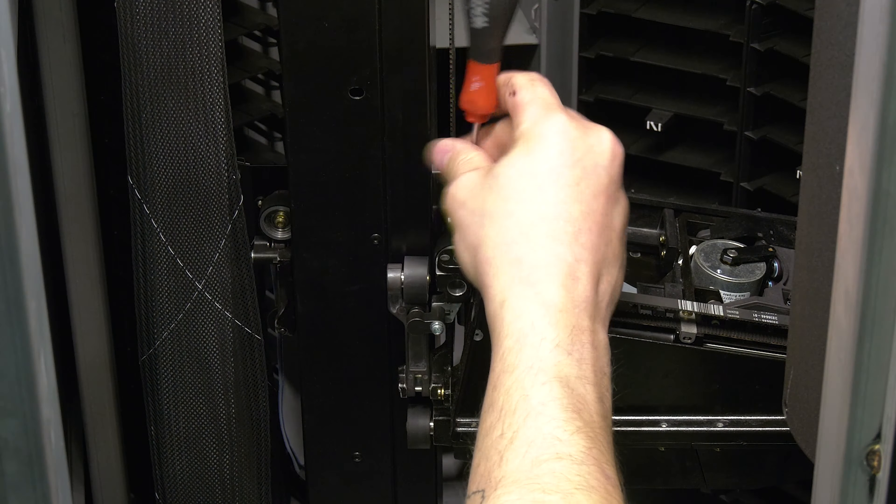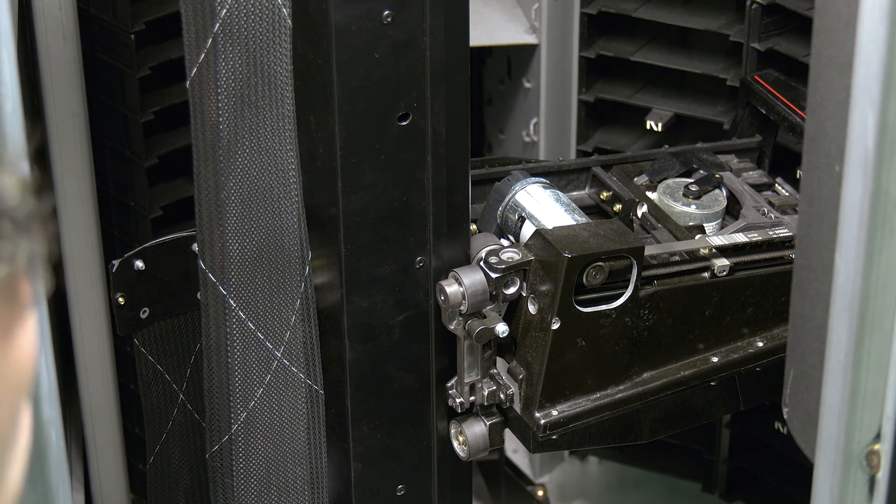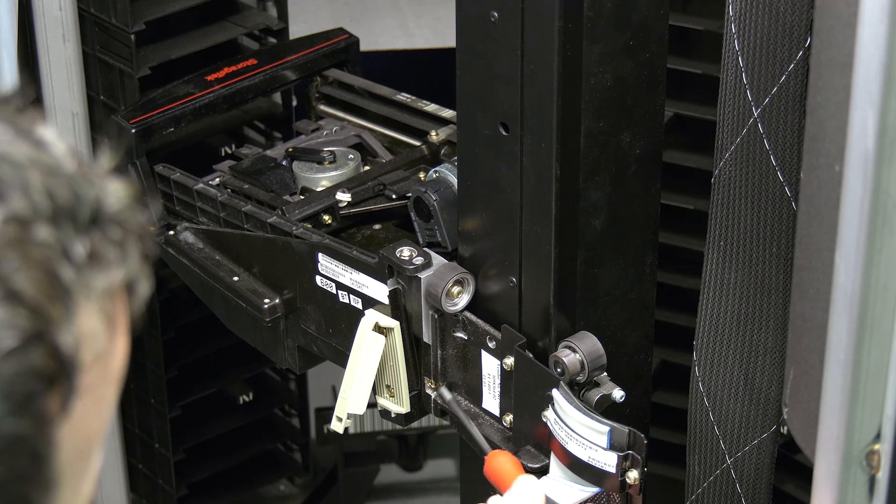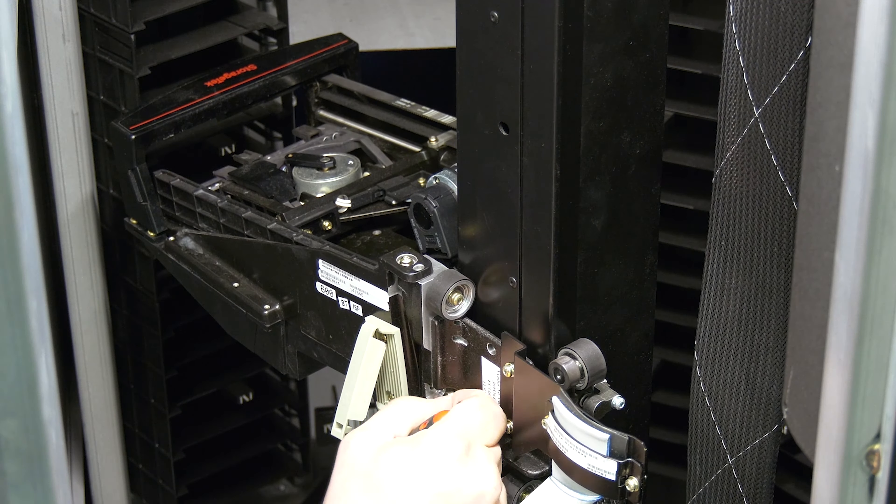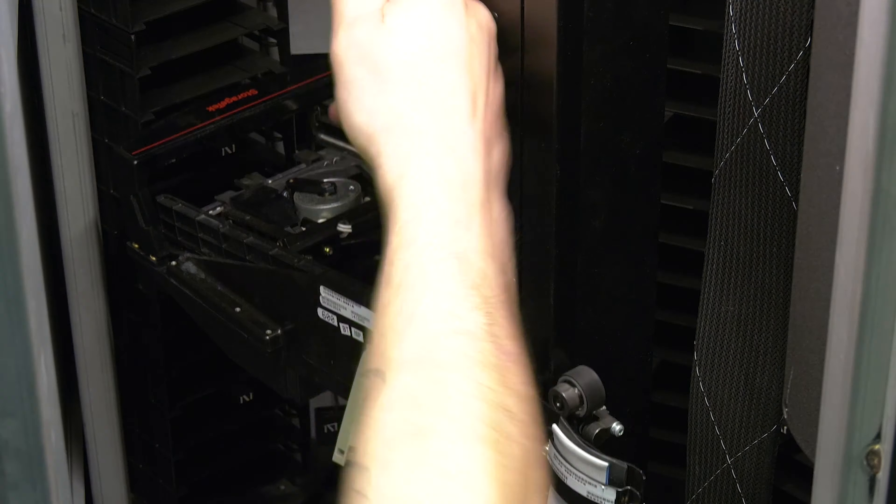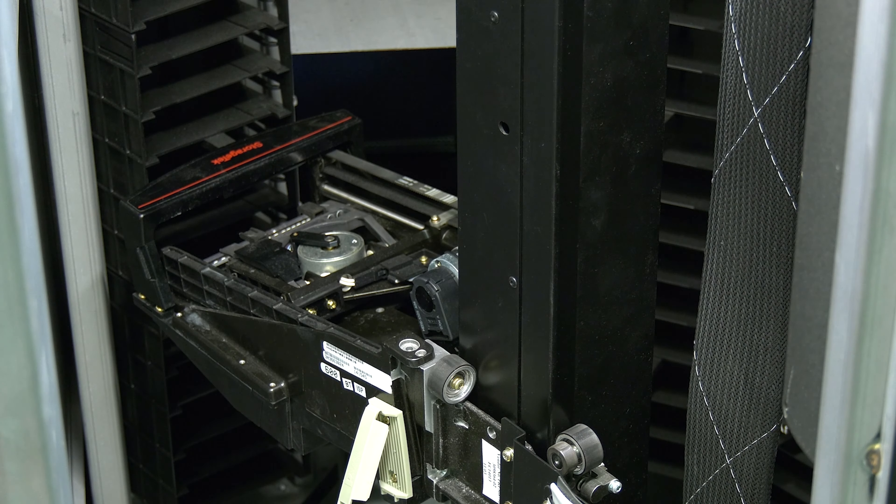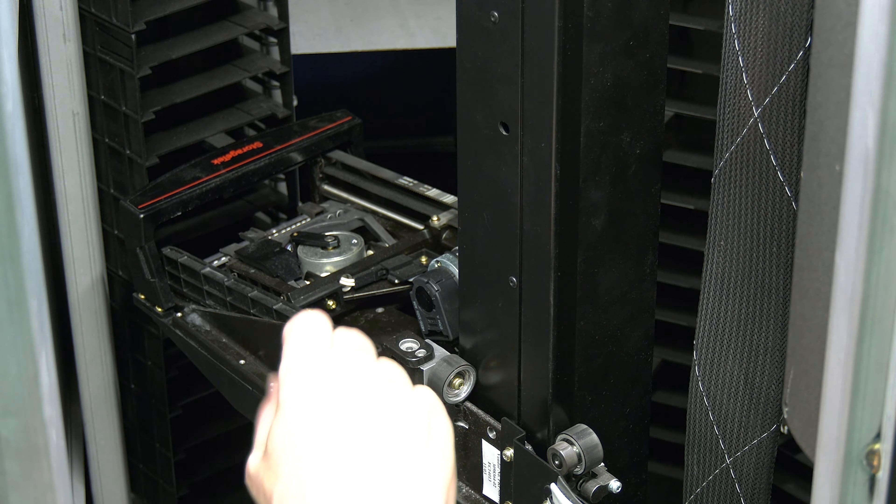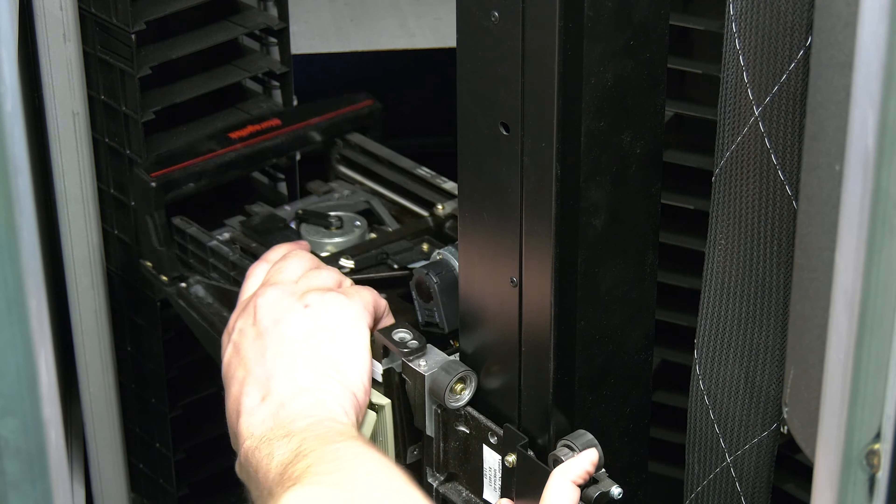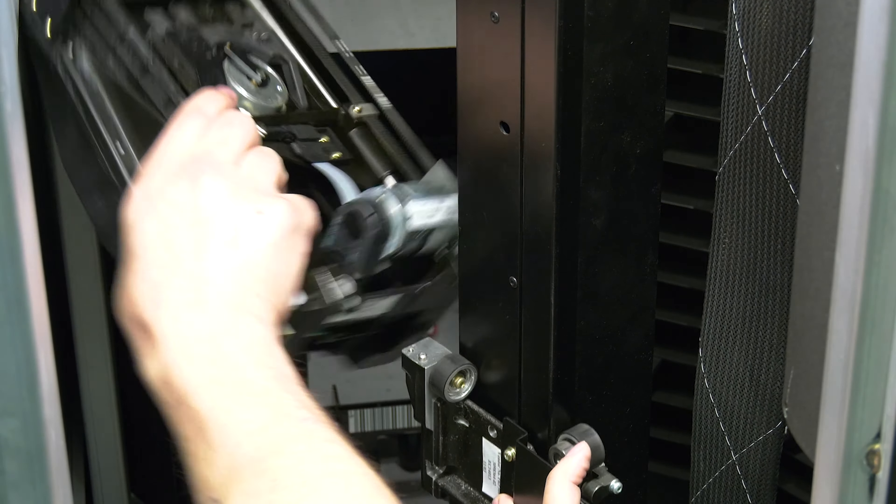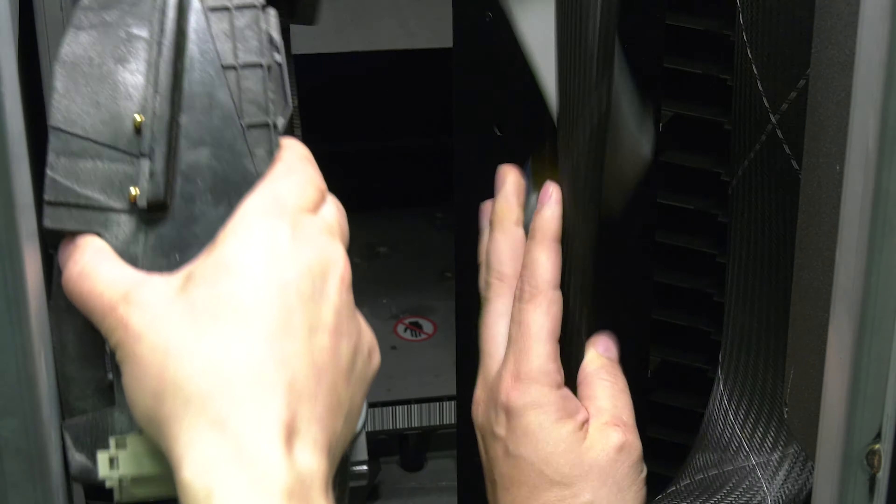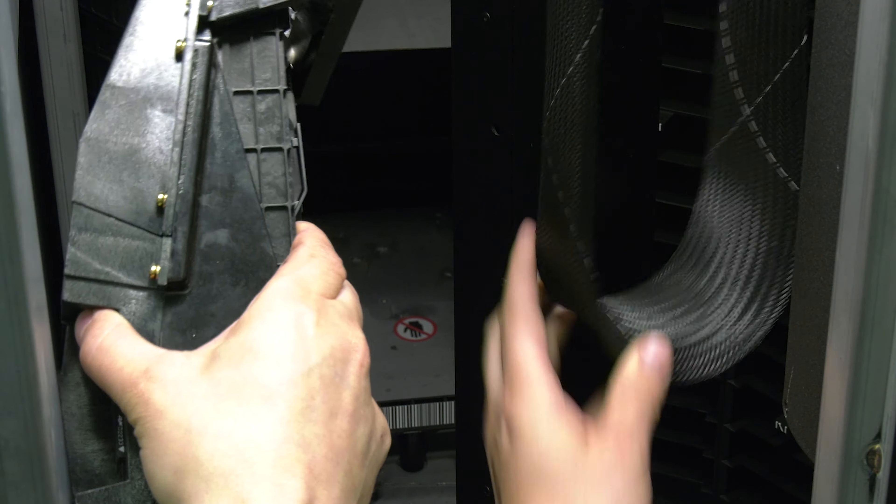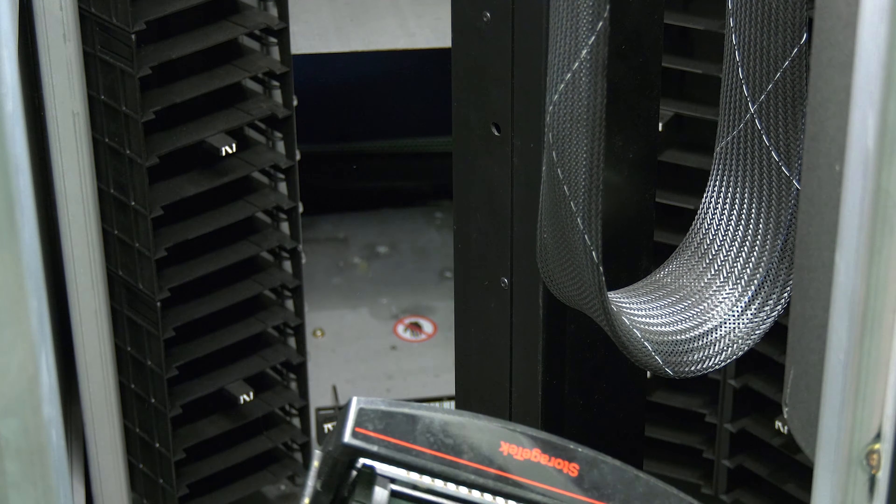Now you will need to remove the four screws that hold the picker in place. There will be one on each side of the rear of the picker and two on the top of the picker. Once these are all removed, you can take hold of the picker with one hand and the vertical axis mount with the other, and carefully lift the picker off the vertical axis mount and set it to the side.